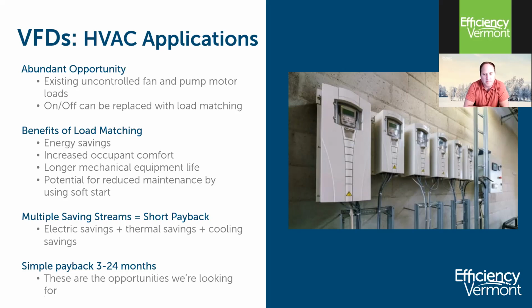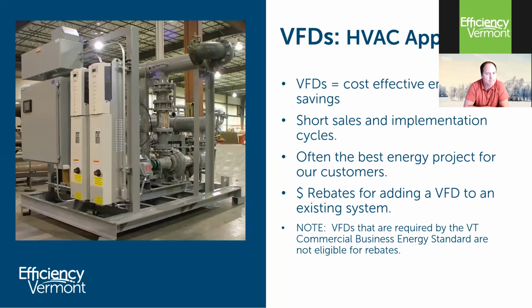All right, if there are no questions, we'll move on, keep rolling here. We talked about cost-effective energy savings. We can do a 400 light retrofit project, or we can put a 40 horse VFD in and secure about the same amount of savings in a single line item transaction. So the sales cycles can be shorter, and the implementation cycles can be shorter. Especially when you're dealing in the HVAC realm, you're dealing with mostly 50 horse and under drives. Those are predominantly off the shelf drives in normal times.